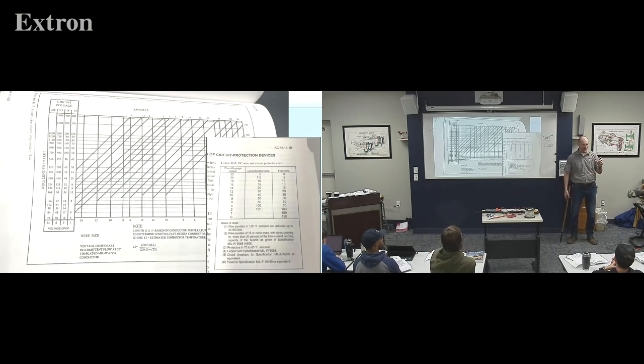So if you have a high inrush that then drops back down again, like when I start a motor, we're okay again. The circuit breaker can handle that and won't just trip immediately - it's like, yeah, that was a high inrush, but it went back down. Fuses typically don't have that capacity; they'll trip a little faster. So then people will put a larger fuse in to handle it, and now we're going down the road of being less safe.